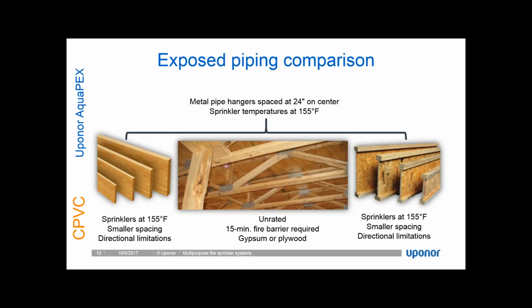This means that they'll have to put a 15-minute fire barrier underneath to act as a lid to separate the unfinished area from where the piping is installed. This fire barrier can be gypsum or it can be plywood. The rules for the 15-minute fire barrier come out of the International Residential Code. You're looking for section P2904.